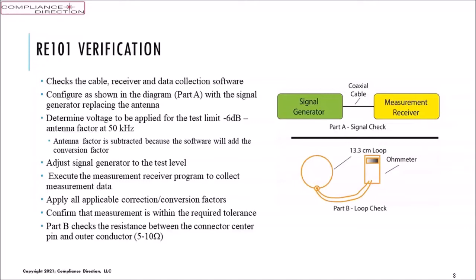So the software is going to apply those antenna correction factors or conversion factors. So we need to have that signal low enough to allow that to be added and still measure at the 6 dB below the limit point. Adjust the signal generator, make sure everything is working right, apply the factors, confirm the measurements are correct, and then we do part B of the check, where we put an ohmmeter between the connector center pin and the outer conductor, and it should read 5 to 10 ohms.